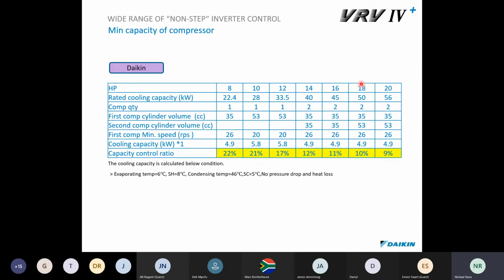But essentially, you can still do a maximum of three 18s together. And the reason we stick to three 18s together is because of the gas laws allowed in international standards, but in particular in Europe. As you know, our product comes from Europe. The reason is that there is a certain amount of charge that's allowed in a system.